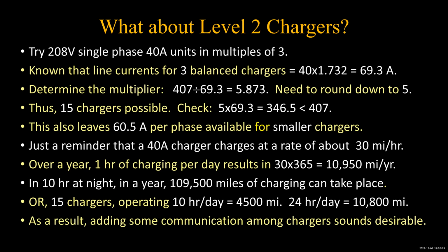The point here, obviously, is you need communication among the chargers, and any decently designed system is going to make sure that the chargers, I mean, there's some of these systems out there, the commercial can have a single controller for 20 chargers, and that's probably going to change. It probably has changed since the last time I looked. So if you got that many on a single circuit, 20 chargers on one circuit for a day, it could very well be adequate. We'll see. What do we got?